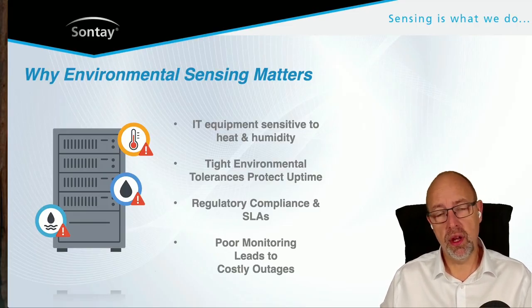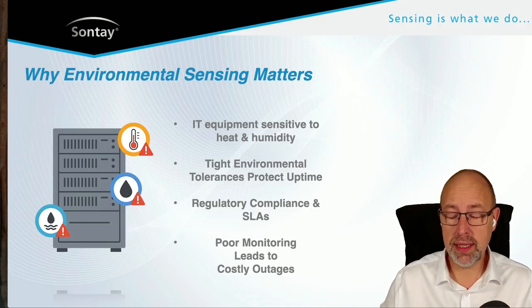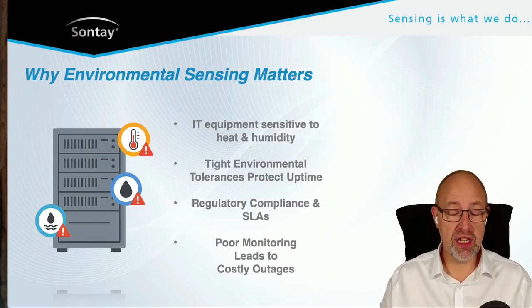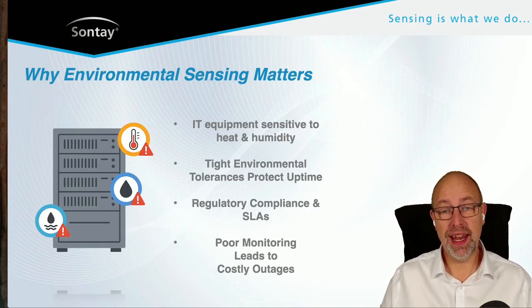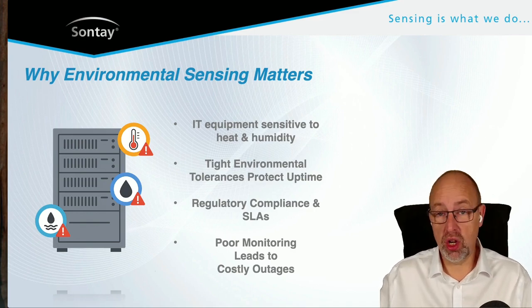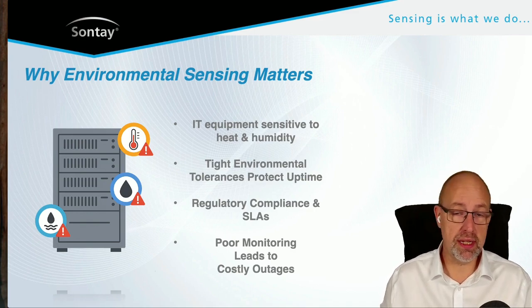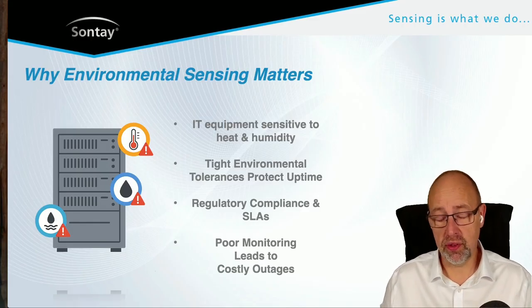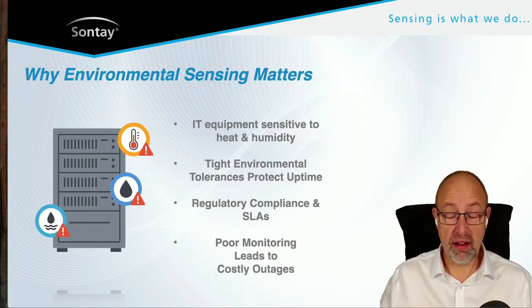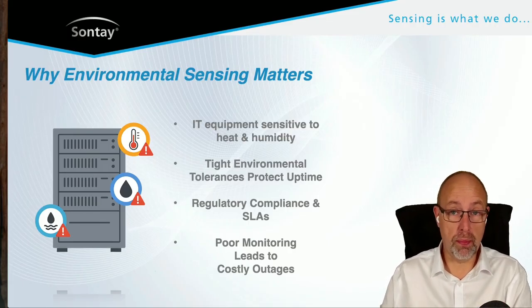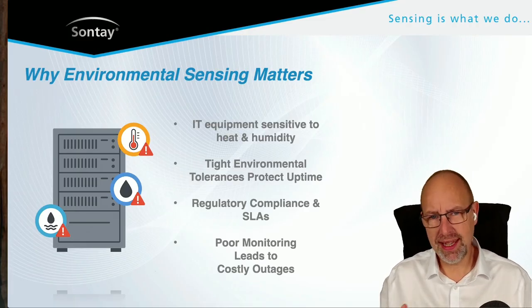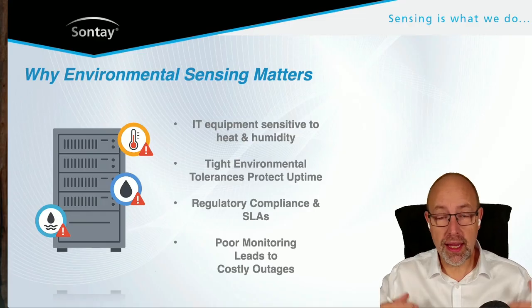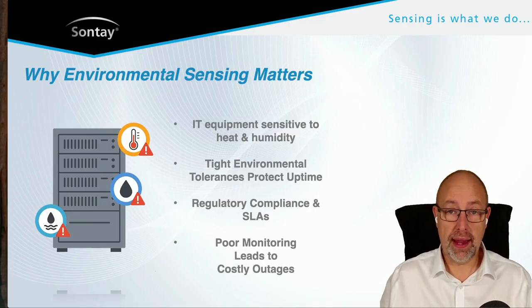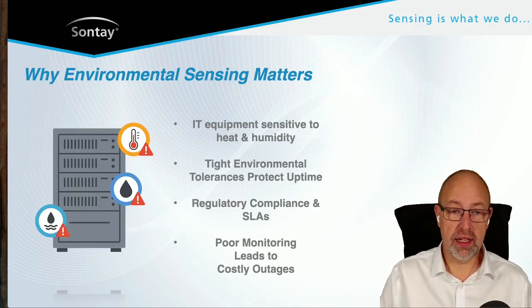The reason is that low relative humidity is an environment in which static discharge happens more easily if you've got a statically charged body. So if you're in a data center and you're statically charged, you're more likely to discharge if the relative humidity is low, and that can damage circuits and servers. So we tend to actually humidify data centers because inherently they have no humidity of their own. There's no people in there breathing to add to the humidity, so we have to add moisture to data centers to keep them humidified, just to prevent that environment where static discharge is likely to occur.